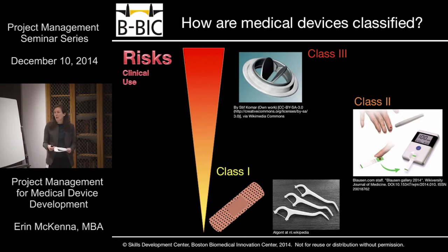History plays a big role in that as well. The FDA will sometimes down-classify a device once there's enough experience. Cardiac balloon catheters, for instance, were down-classified about, I think, 7, 8 years ago now.